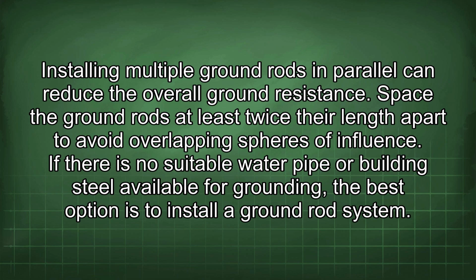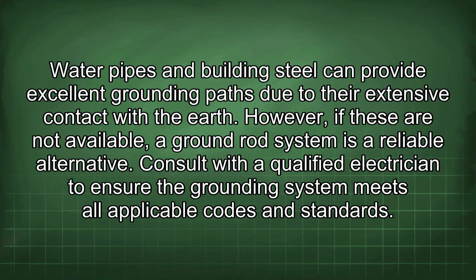Space the ground rods at least twice their length apart to avoid overlapping spheres of influence. If there is no suitable water pipe or building steel available for grounding, the best option is to install a ground rod system. Water pipes and building steel can provide excellent grounding paths due to their extensive contact with the earth. However, if these are not available, a ground rod system is a reliable alternative.